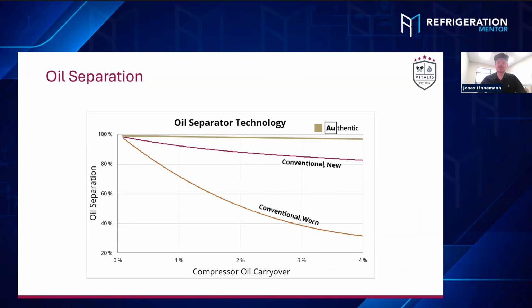Let's look at some results here for a bit. We had a test bench for oil separator cartridges. The existing ones at that time, if they were worn, typically got micro cracks, which affects the separation efficiency a lot. They were very bad. The normal ones, if they were new and clean, still reached a level of up to 90%. You can see here the compressor oil carryover. Typically the oil carryover of the compressor is in the range between 1 and 3%. And with the improved design, we have seen a very high, stable separation ratio.